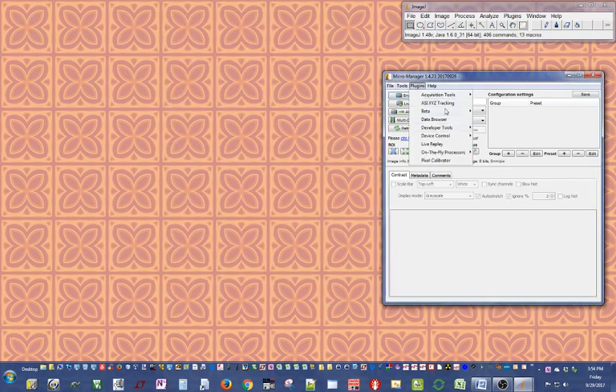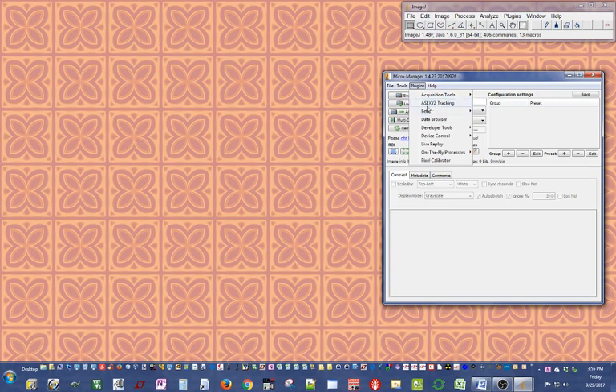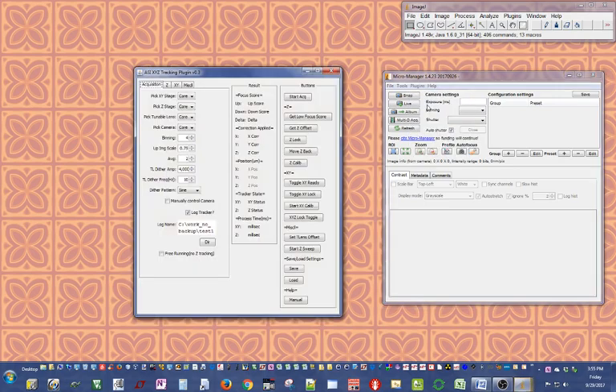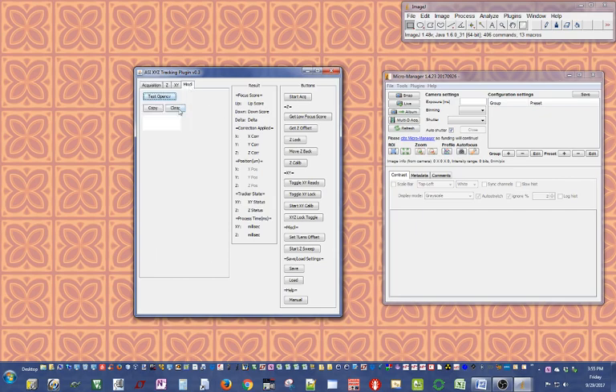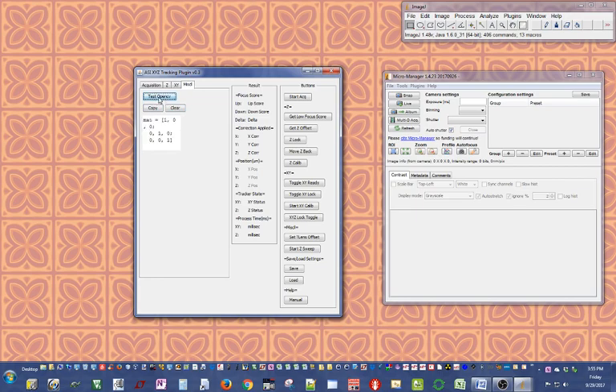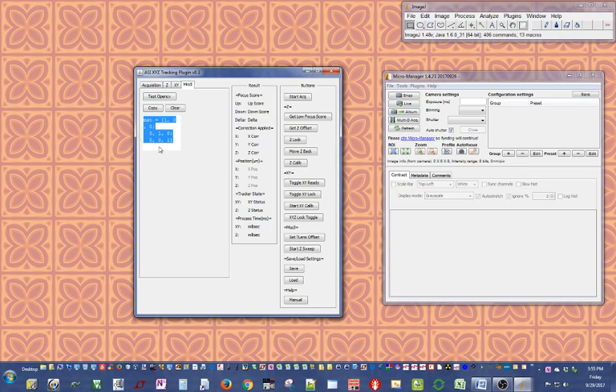The plugin runs - that's where we put the plugin, right, in the plugin folder, MM plugin folder, so that's available to us. The plugin runs but we can't pick any stage. Just to be sure the plugin is installed correctly and OpenCV is running properly, in the miscellaneous section of the tab I have a button for testing OpenCV. Running it, pressing it runs a small snippet of the code. It's called an eye matrix and that's what it's supposed to look like. If you don't see this and you see an error instead, that means we need to troubleshoot. Contact ASI and we can help you out with that.